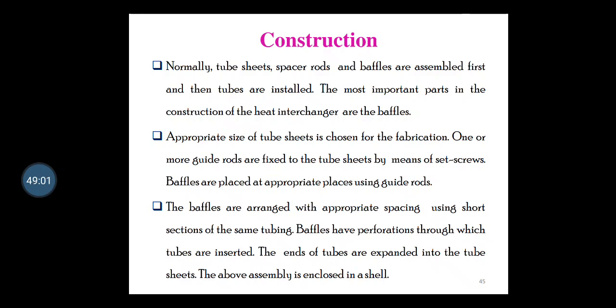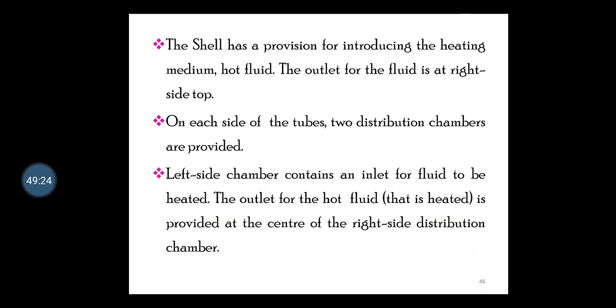The baffles are arranged with the appropriate spacing using short sections of the same tubing. Baffles have perforations through which the tubes are inserted, and the ends of the tubes are expanded into the tube sheets. So the above assembly is enclosed in a shell. The shell has a provision for introducing the heating medium, the hot fluid. The outlet for the fluid is at the right side top.